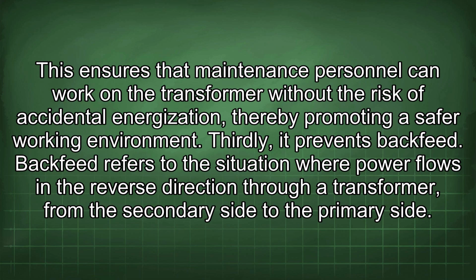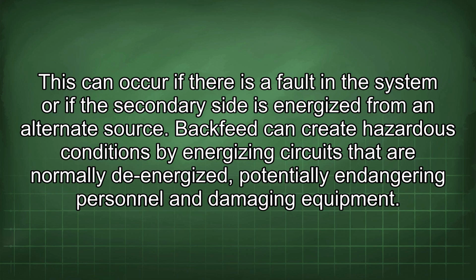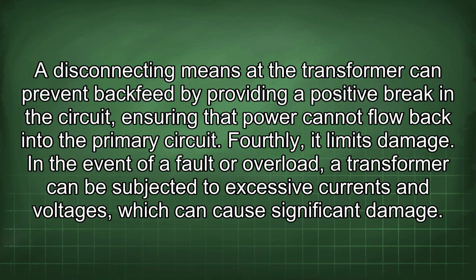Backfeed refers to the situation where power flows in the reverse direction through a transformer, from the secondary side to the primary side. This can occur if there is a fault in the system or if the secondary side is energized from an alternate source. Backfeed can create hazardous conditions by energizing circuits that are normally de-energized, potentially endangering personnel and damaging equipment. A disconnecting means at the transformer can prevent backfeed by providing a positive break in the circuit, ensuring that power cannot flow back into the primary circuit.